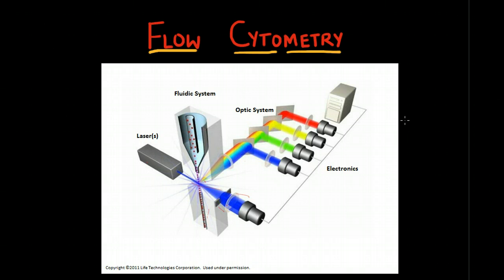How does the flow cytometer work? We have the beam of light right here, which is of a single wavelength, and it is directed onto a hydrodynamically focused stream of liquid containing a single file of cells. This is achieved by the sheath fluid.